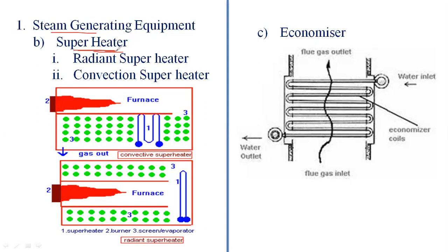Due to the superheater, we are using the flue gases through the superheater, economizer, and then air preheater. We are improving the efficiency by 5 to 10%. Actually, in the thermal power plant, the losses are 71%. In the boiler, the loss is 16%, the turbine loss is 54%, and the alternator loss is 1%. That is 71%, so the efficiency we are getting is 29%.